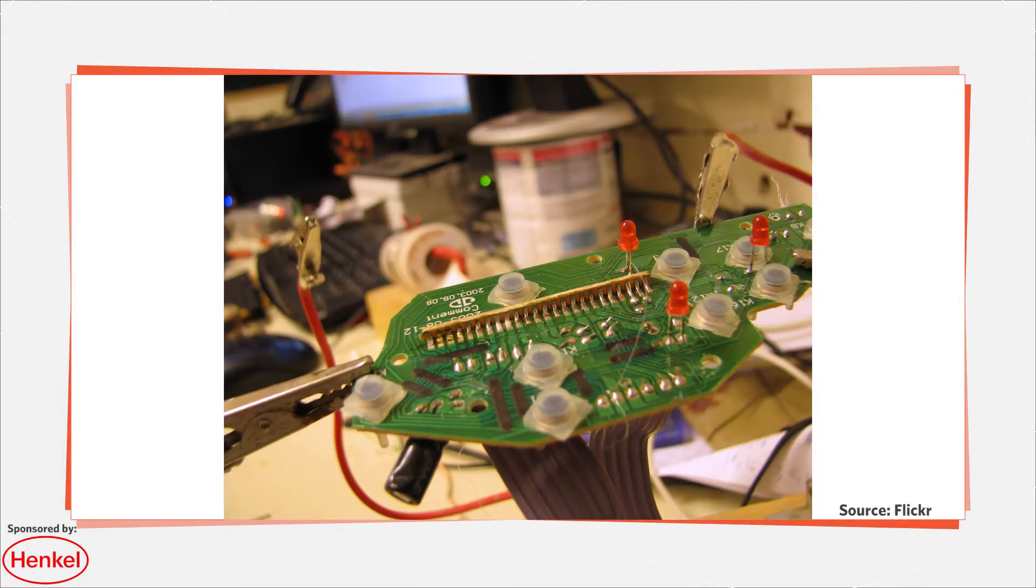Membrane switches are also submersible in water. One major cause of membrane switches failing is improper sealing of switch layers. The top layer of membrane switches contains the graphic interface that helps the user communicate with the machine. The underlying layers are circuitries that are typically created using screen printing.